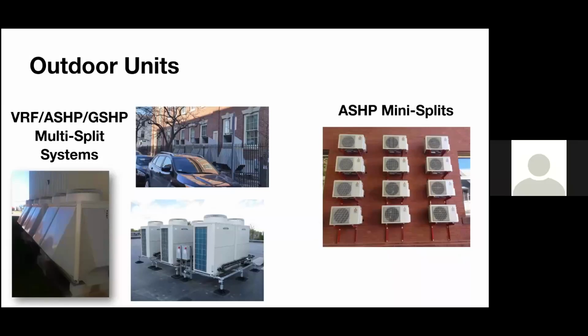So looking on the left-hand side, the bottom picture of the VRF equipment, this is actually 40 tons of equipment. So this would be more of a central approach to a building, just running refrigerant lines maybe in the center of the building, and then sporadically putting them out onto different sections, right? So this is 40 tons. This is a good install. As you can see, they're up on stands, which Adam has mentioned.